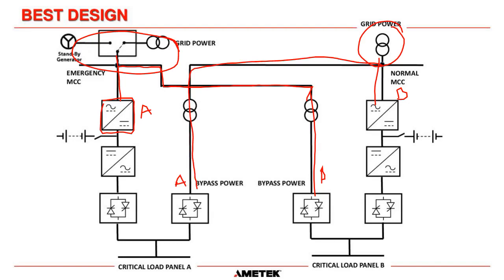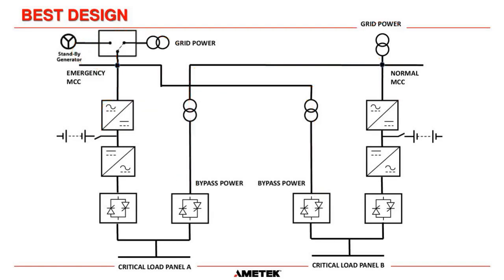So they are cross-connected. And what that allows you to do is, let's say for some reason the plant is doing maintenance on the MCC that feeds the normal board. Then you know that you have an emergency board which is going to be unaffected, which allows this UPS to feed critical load panel A, and also that will feed the bypass for this system over here. So both load panels will be supplied, even if you have a complete MCC failure. Okay. And the other good thing about this situation is, once again, we have 4 static switches available, so they are not single points of failure.